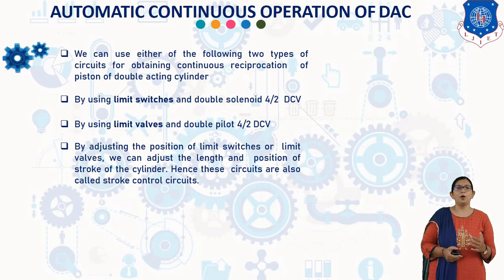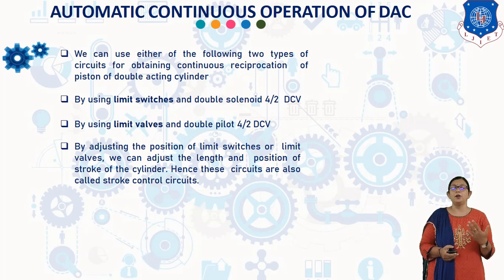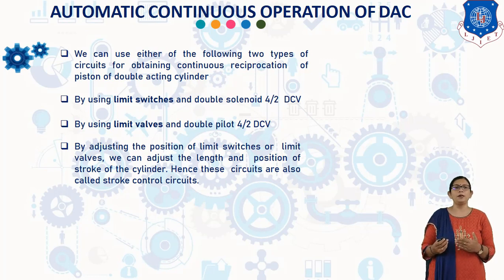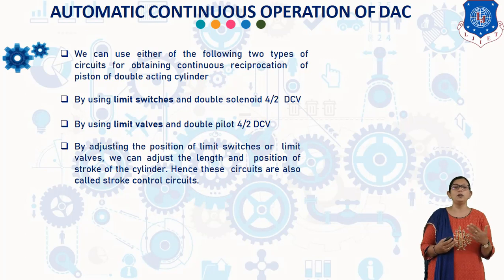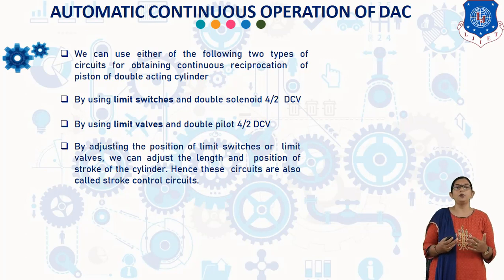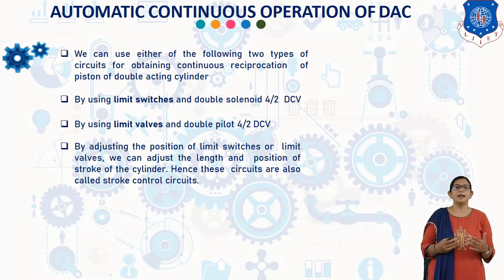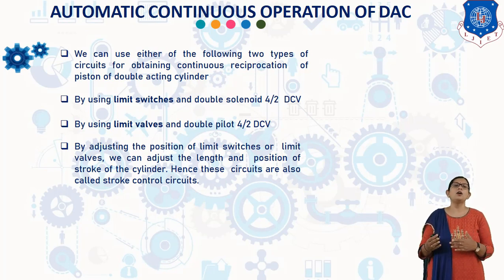Now we will discuss the automatic continuous operation of a double acting cylinder, generally known as DAC. We can use either of the following two types of circuit for obtaining continuous reciprocation: first, by using a limit switch and double solenoid 4/2 DCV; second, by using a limit valve and double pilot 4/2 DCV. By adjusting the distance of limit switches, we can also adjust the length and position of the stroke of the cylinder. Hence, these circuits are also known as stroke control circuits.